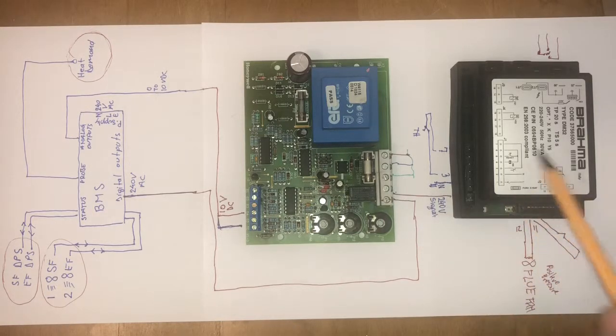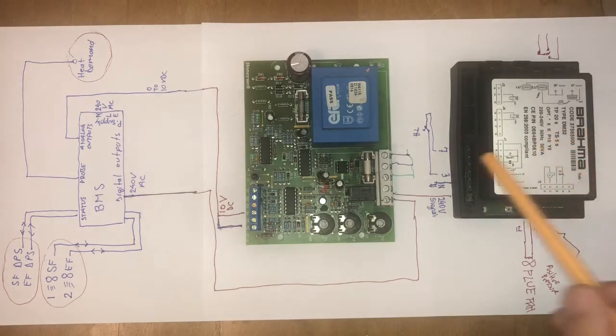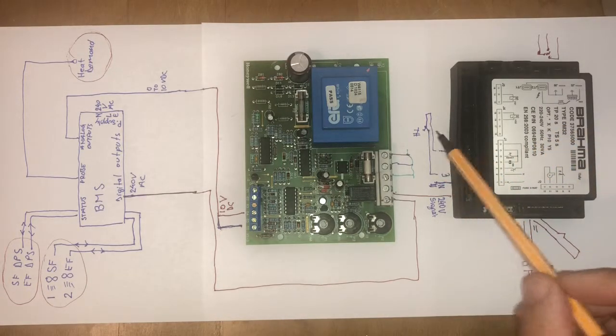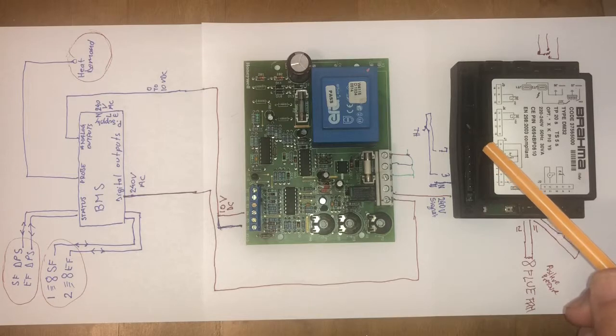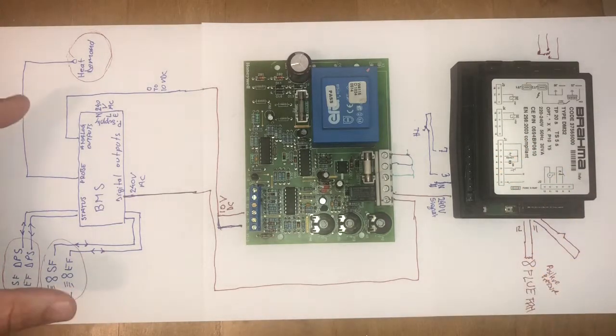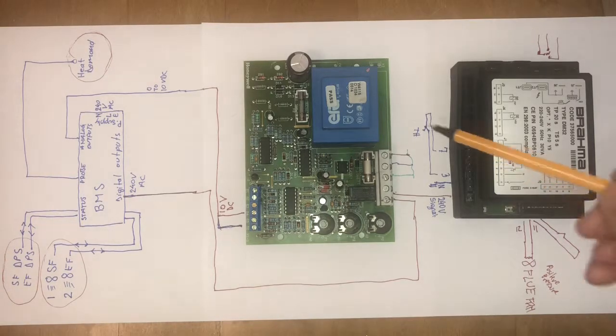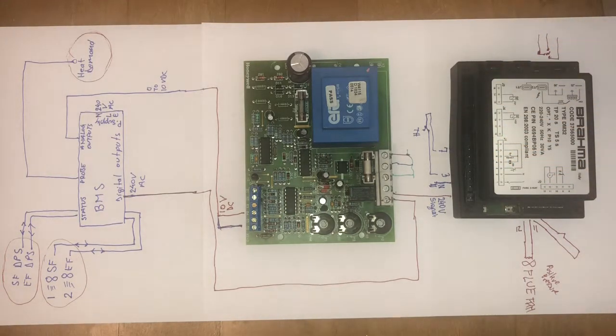And then the controller will initiate if the thermostat is on heat demand, because sometimes the building management control will hold off the heating in a building to save energy, despite the thermostat in the wall screaming for heating because the building is too cold. There's a lot of illogical things which I always explain to my managers and to the people I work for, about 10 years, but I'm not going to go there right now.